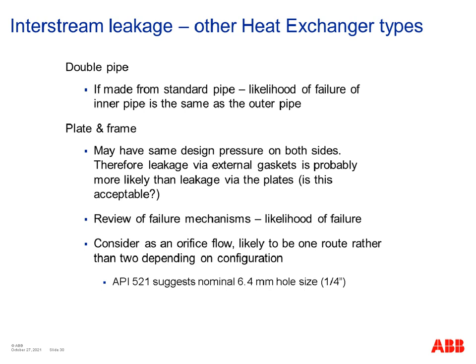So if you don't consider it credible for a pipe to suddenly fail with loss of containment on the plant, then you wouldn't consider it to be credible for the pipe internal to the heat exchanger to fail in the double pipe scenario. So that's sometimes a design that operators will go towards if they really want to rule out the tube failure case, if they have a massive differential pressure between the HP and the LP side, and they know the consequences of a tube failure are going to be very serious, then they might go for this double pipe design to make it not credible. So that is an option.